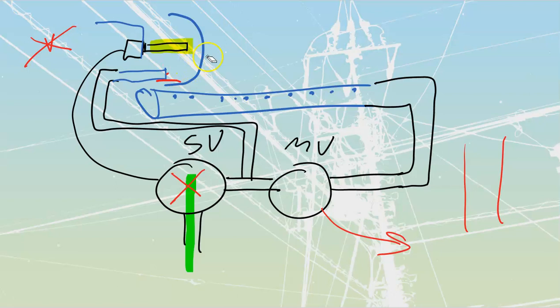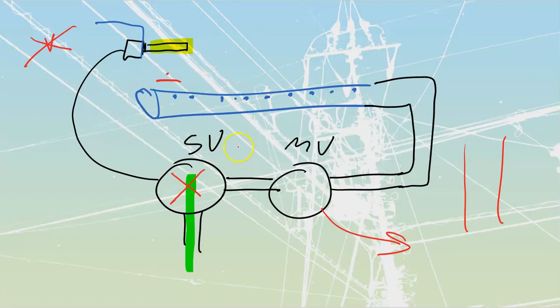Now, we don't have pilot lights for everything. We've got a couple of other types of devices that use what we refer to as igniters. An igniter is going to start up the gas. We don't keep a pilot light running inside of there. There are two main types. We have DSI, which stands for direct spark ignition. It's like the spark plug inside of your vehicle. Basically, there will be two points of high voltage, and in between those two points we will strike an arc, and that arc will be directly across one of my jets. When it goes across there, it's going to light that gas. That's your direct spark ignition. The other one that we have is referred to as a hot surface igniter.